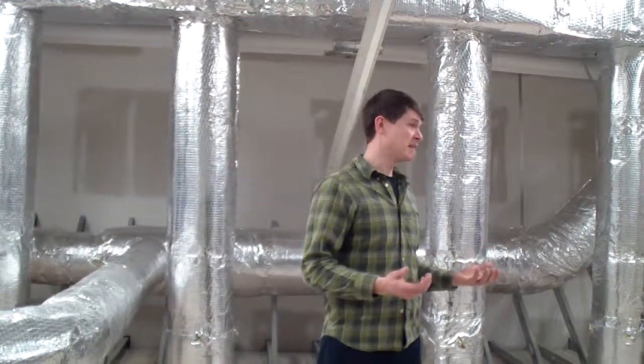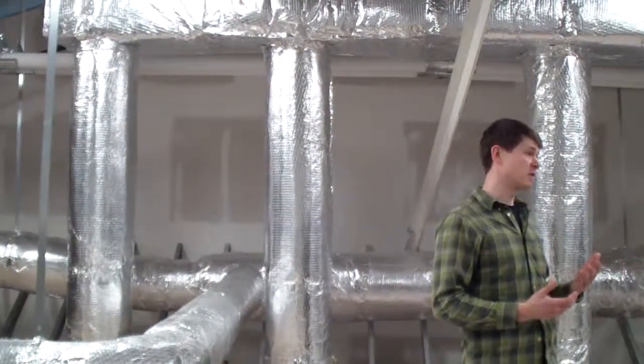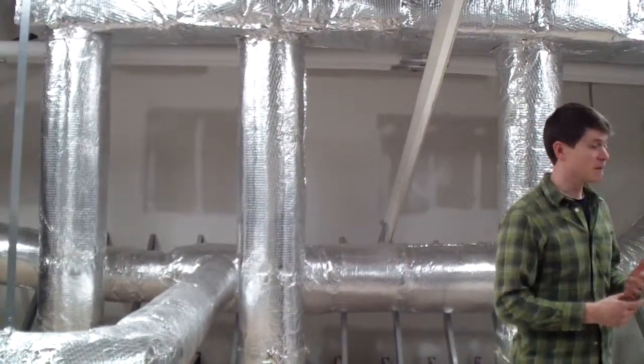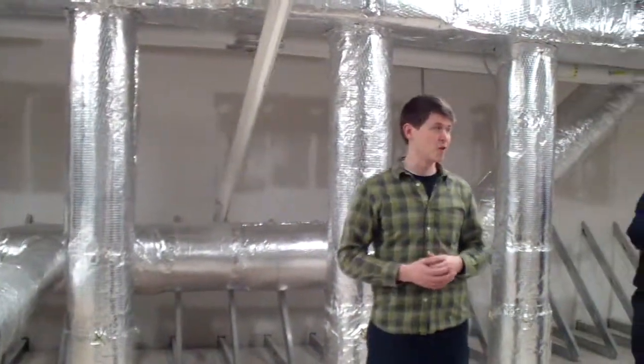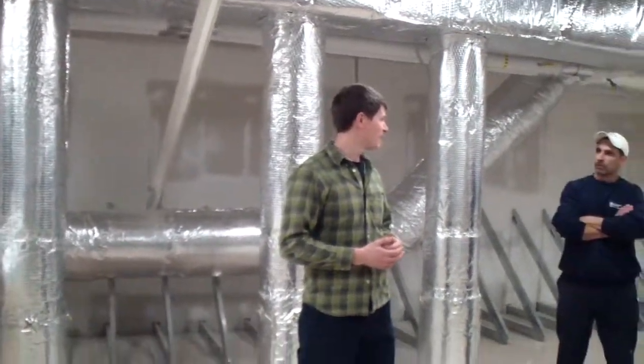So if for some reason you find out you're not getting any flow, maybe the damper's closed, maybe the air handling unit's off. Both of those things you can actually see through software. And if you can't tell through that, then obviously you have to do the old-fashioned method. Come up and measure.